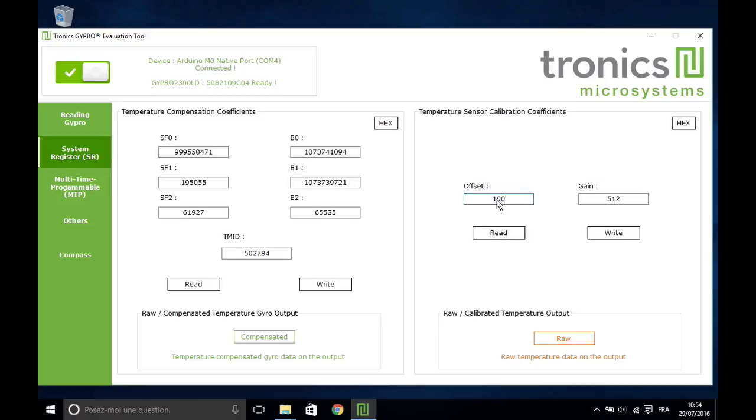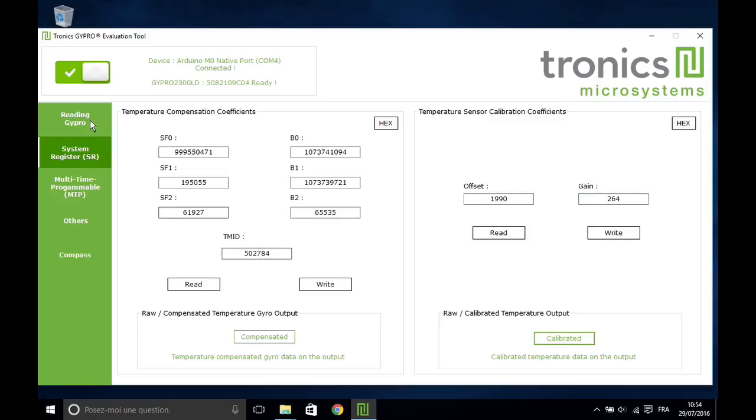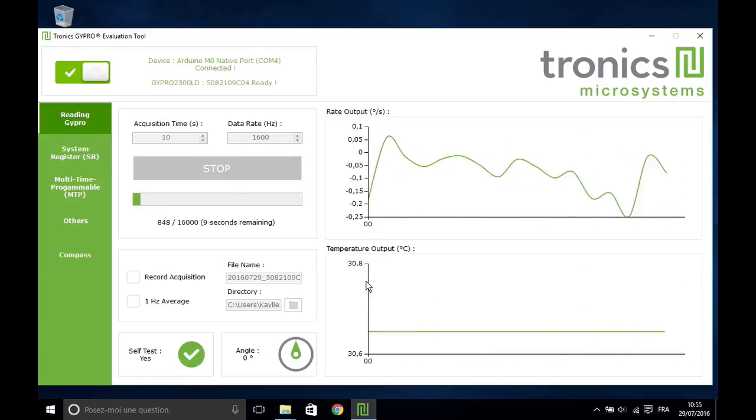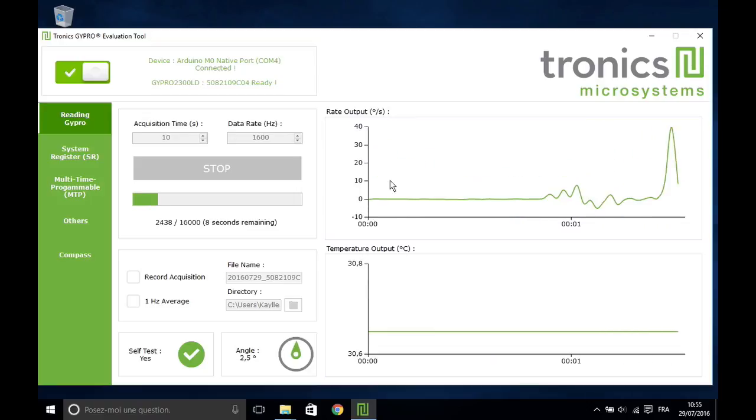Enter offset and gain values. Write them into the System Register and switch to the calibrated temperature output. On the real time chart, the temperature is now displayed in Celsius degrees.